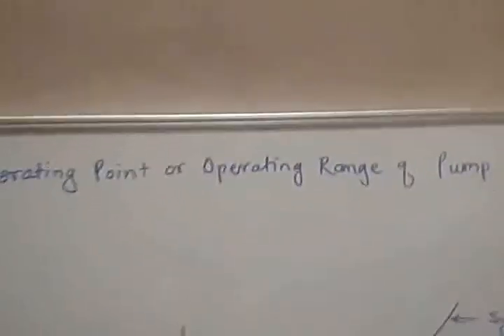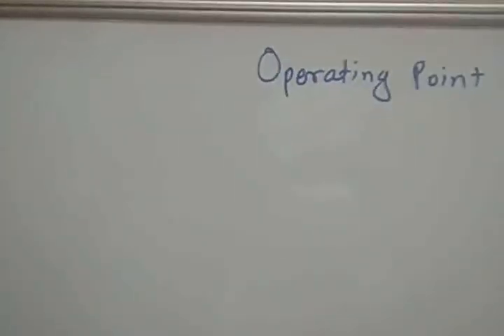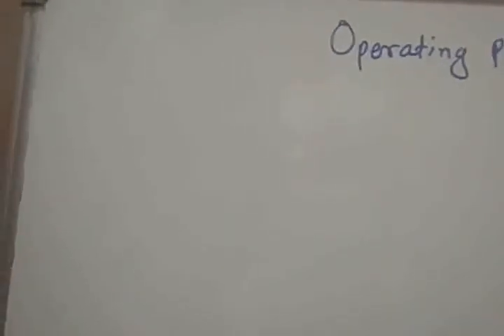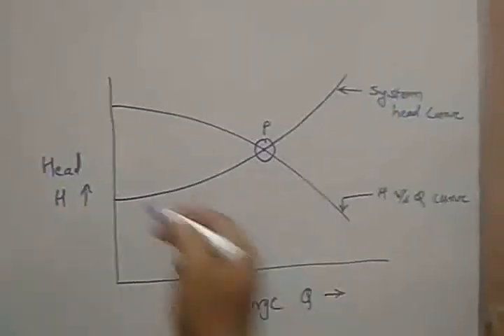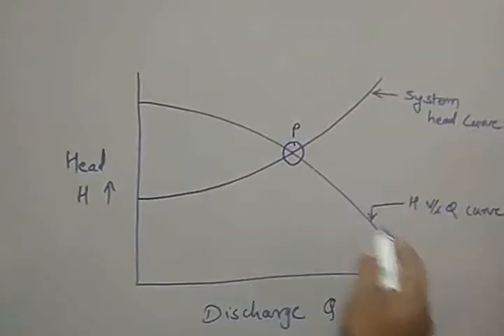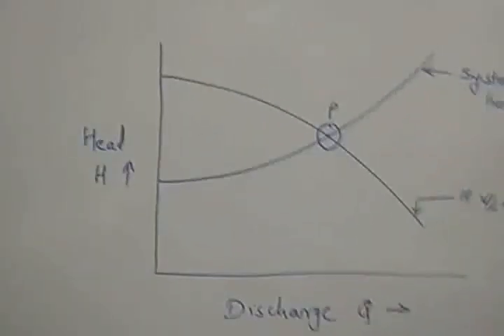Now, we will see the operating point or operating range of a centrifugal pump. The operating point of a centrifugal pump is the point of intersection of the system head curve with the head-discharge curve. I have drawn the plot — you can see the system head curve and the head-discharge curve, and the intersection point of these two curves is the operating point P.